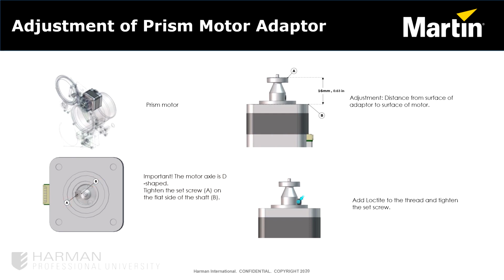On the prism motor, there is a D-shaped shaft, as on many others, so ensure that the set screw is on the flat spot of the shaft and that the distance from the surface of the adapter to the surface of the motor is 16 millimeters.